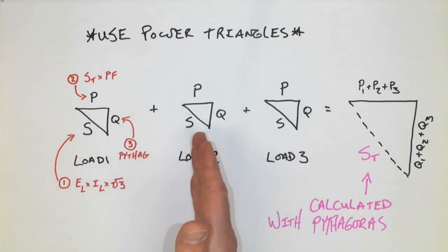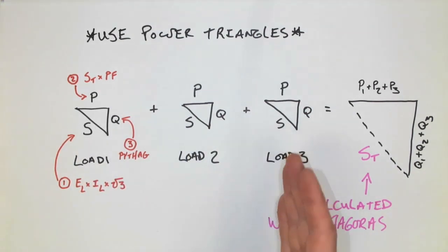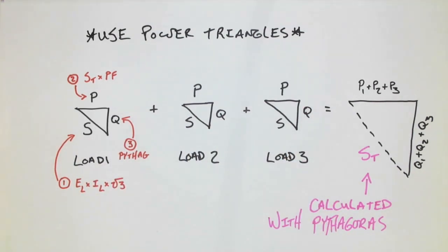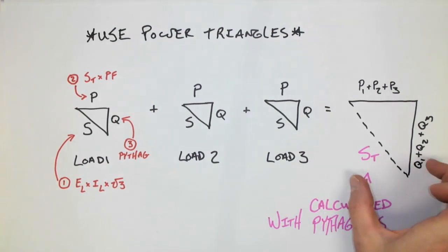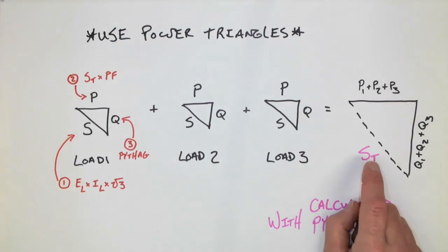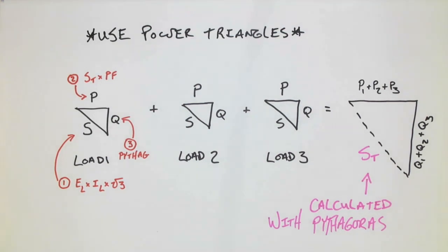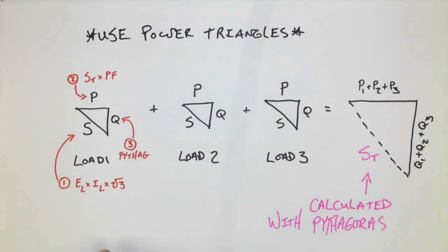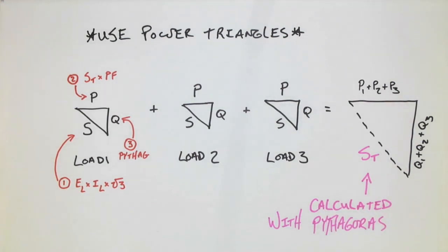After I've calculated the horizontal and vertical component of each load, we then move on to the total. From here, I can then calculate the VA total for the entire system, and I could also work out the total line current. Because remember, S total is equal to E line times I line times root three. So let's take a look at our first example.